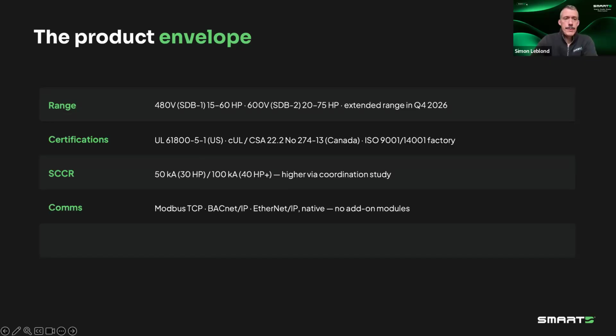We have embedded communication, so Modbus TCP, BACnet IP, and EtherNet/IP are all native, so you don't need any add-on modules or hidden cost. It is a NEMA 1 wall mount package, so you don't necessarily need a panel, and they are rated up to 50 degrees C without derating. So you can go into quite hot environments and potentially lower your cooling requirement in that VFD room. And our standard warranty is 18 months, with the potential to extend that if the install is done by a certified partner.